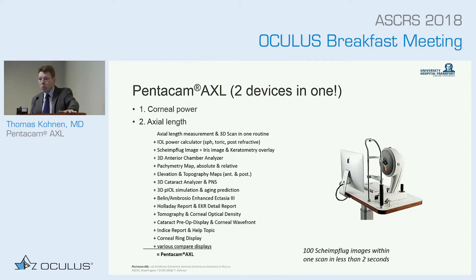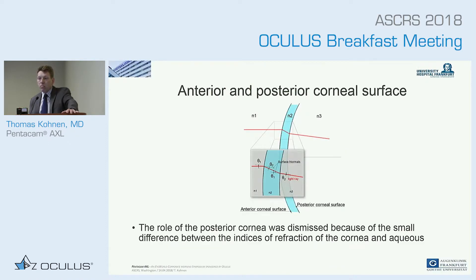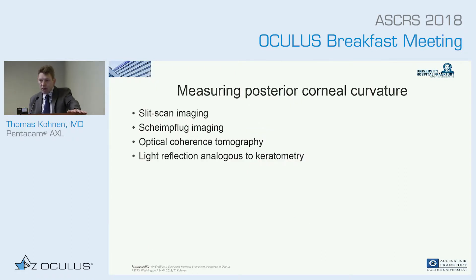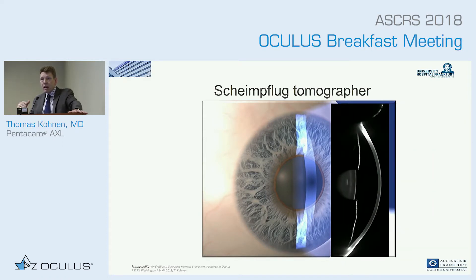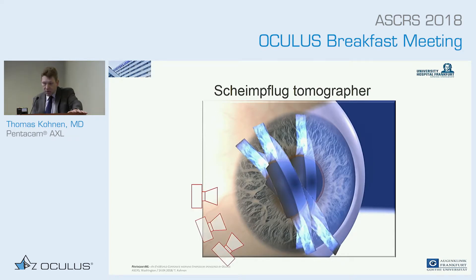Jack pointed out the report nicely, but I will go to the background of what we have done over time. The role of the posterior cornea was dismissed because of the small difference between the indices of refraction of the cornea and aqueous, and we had no option to measure the posterior corneal surface. I want to highlight the Scheimpflug imaging device — a Scheimpflug tomographer. This is the schematic drawing of the Pentacam, which takes a measurement of the anterior chamber. It works by taking a lot of slits and putting the picture together.